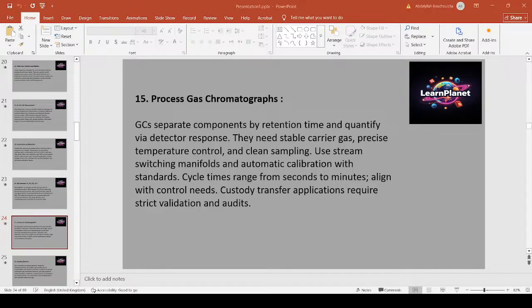Gas chromatographs separate gas mixtures and quantify components by retention time and detector response. They are indispensable for composition and BTU calculations. GCs require clean sample systems, stable carrier gas, and controlled oven temperatures. Install stream switching and auto calibration with certified gas standards for reliability and to minimize drift. Cycle times vary. Ensure the GC's analysis time matches control and allocation requirements. Example, in an upstream gas plant, a GC with proven sample conditioning and a fast cycle is used to calculate NGL split and custody transfer allocation.